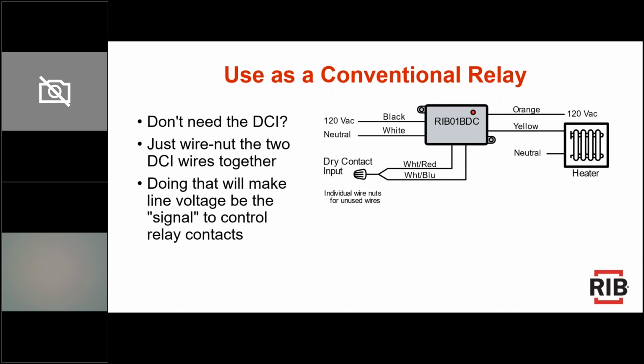Also, not the delay relays, but any of our dry contact input relays can be used as more of a conventional relay, where the signal is the line voltage, the 120 volts. If you don't need the dry contact input, then you can take a wire nut and connect those two wires together, and that makes it so that the 120 volt input voltage is now the signal to turn on and off the relay.